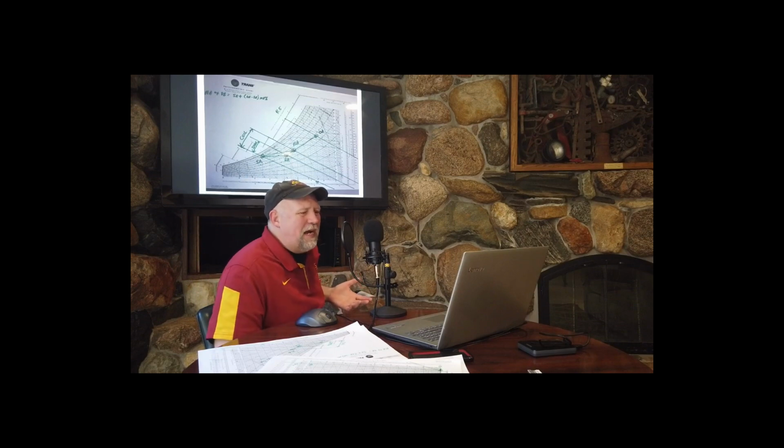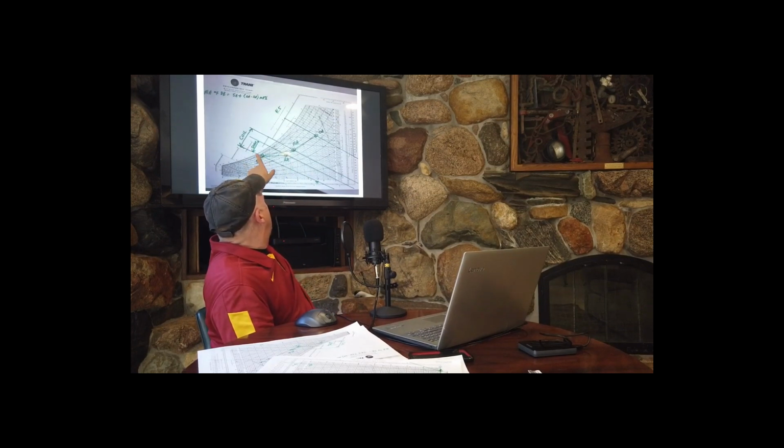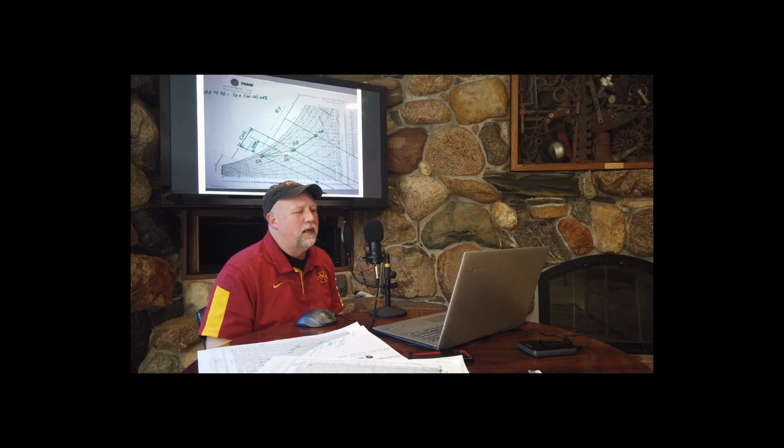That's why the supply air dry bulb is just a few degrees warmer than the supply air wet bulb. There's a way to calculate exactly, but for this class, I just tell you it's about 3 degrees. That's a pretty common difference between wet bulb and dry bulb for the supply air. So 52 wet bulb, 55 dry bulb, and then that air is supplied into the room, and then we start the process over and over again.